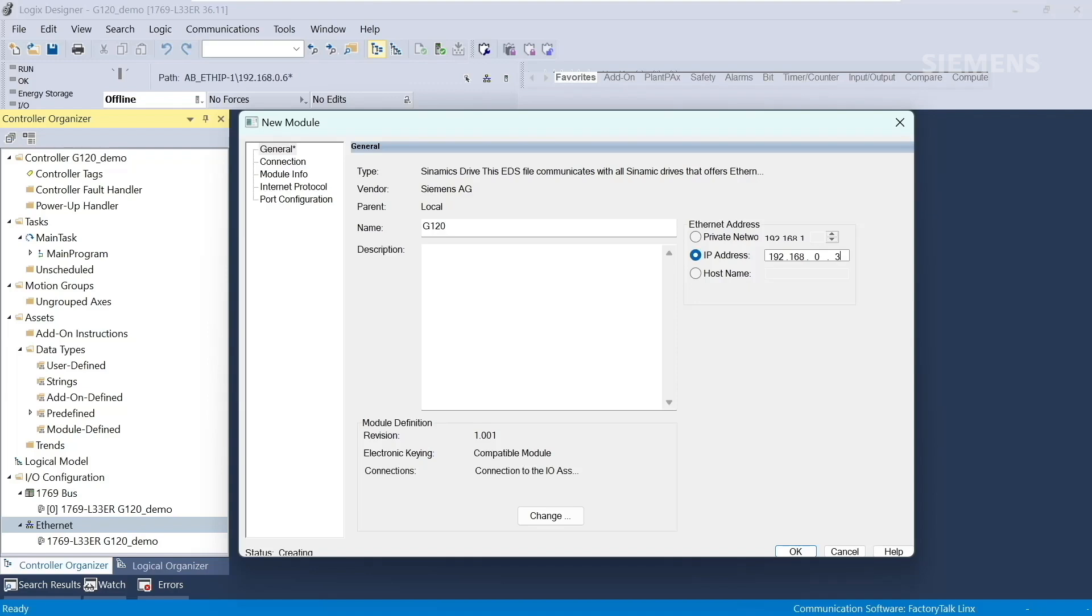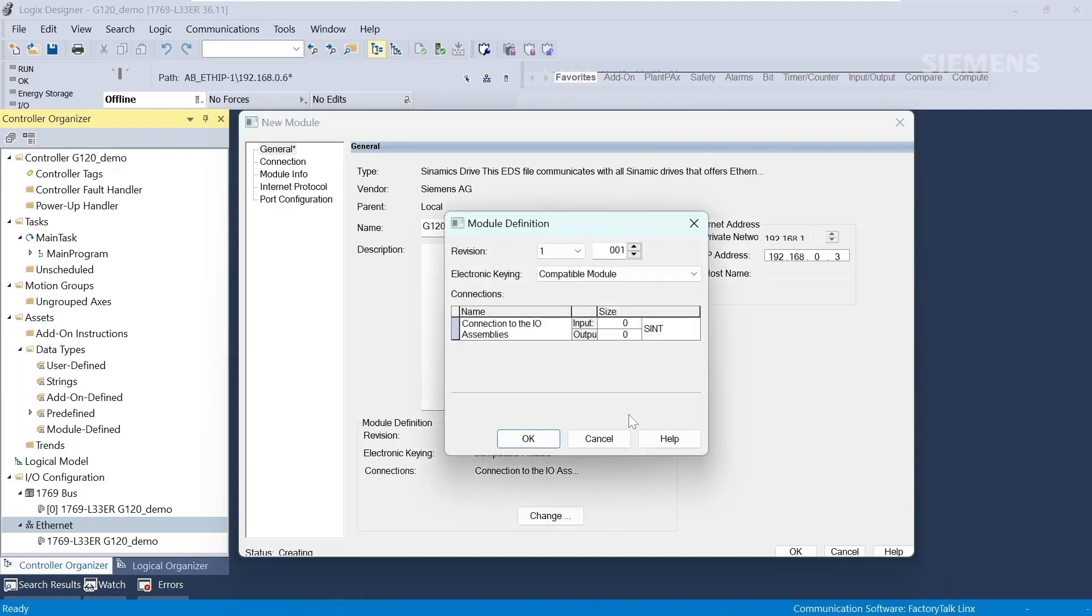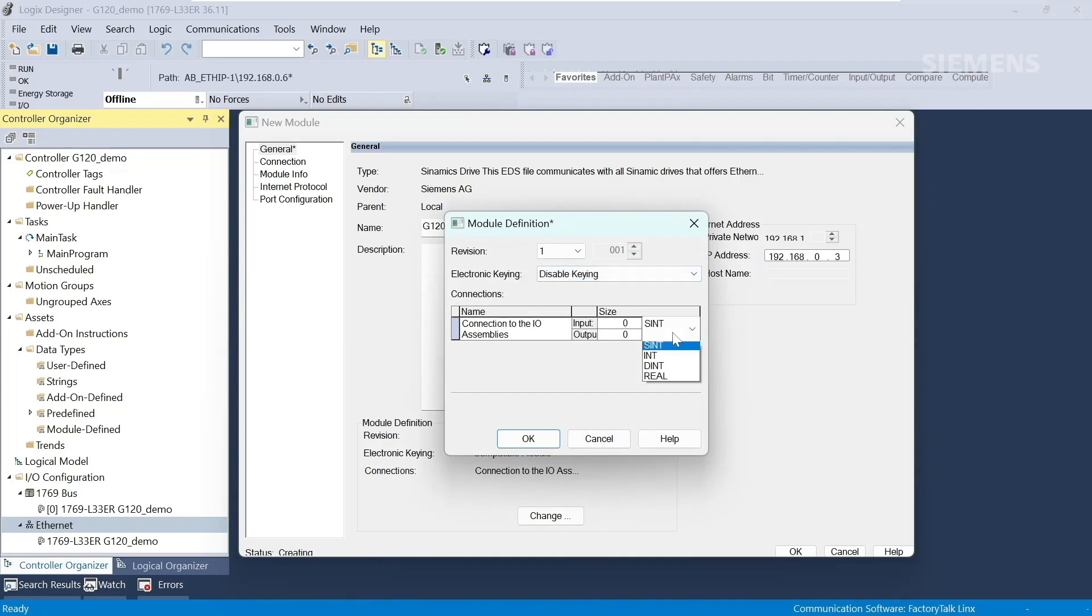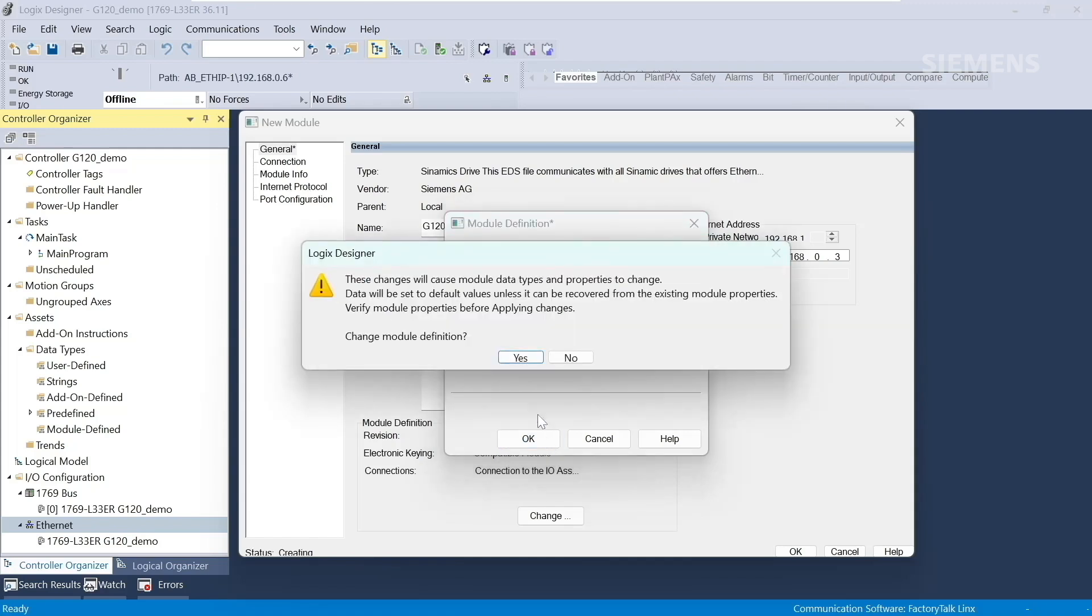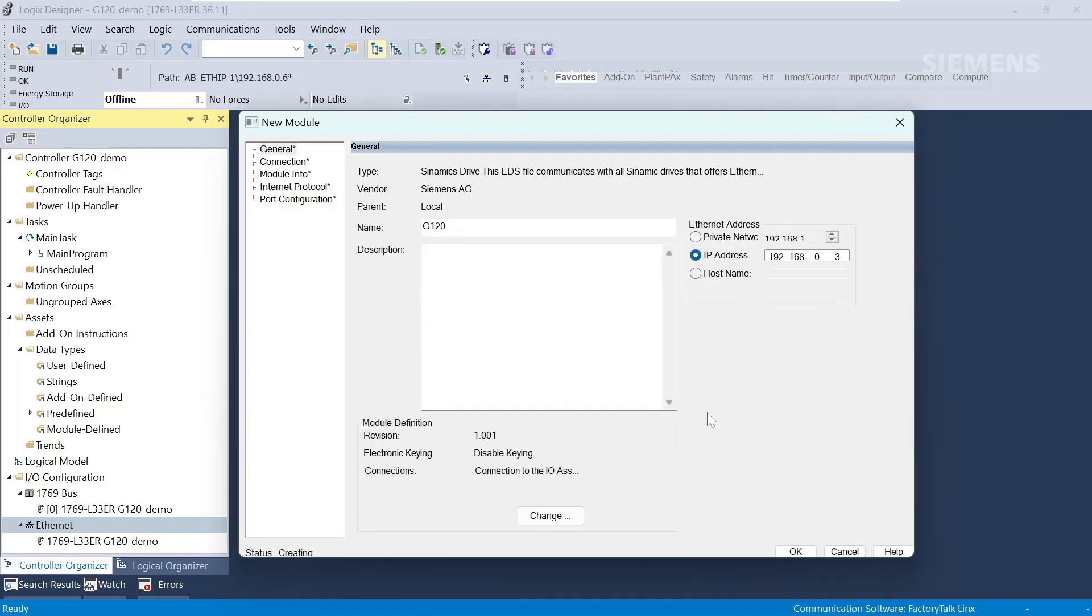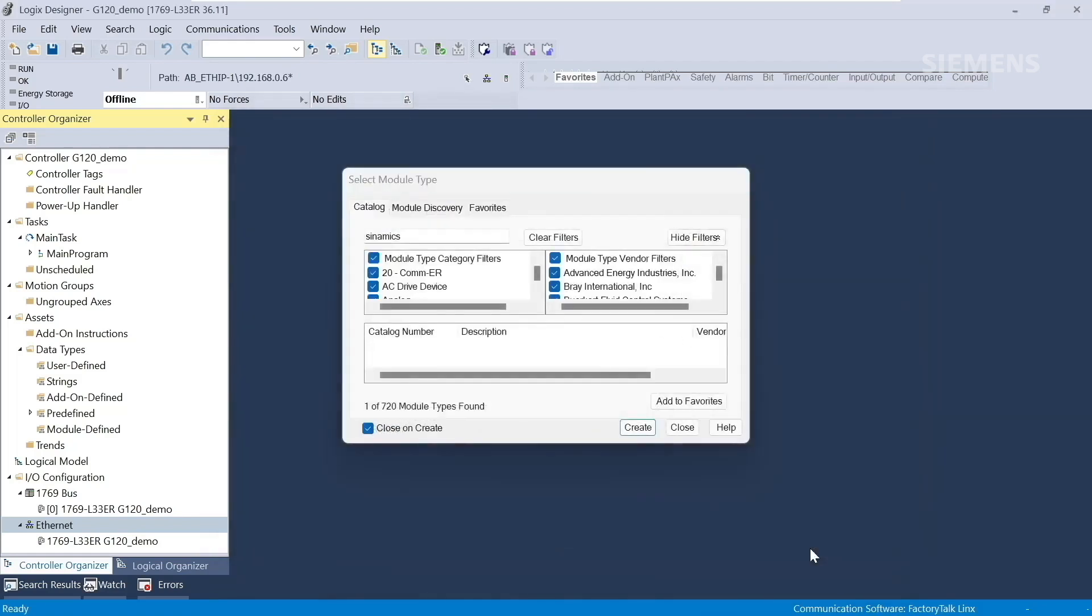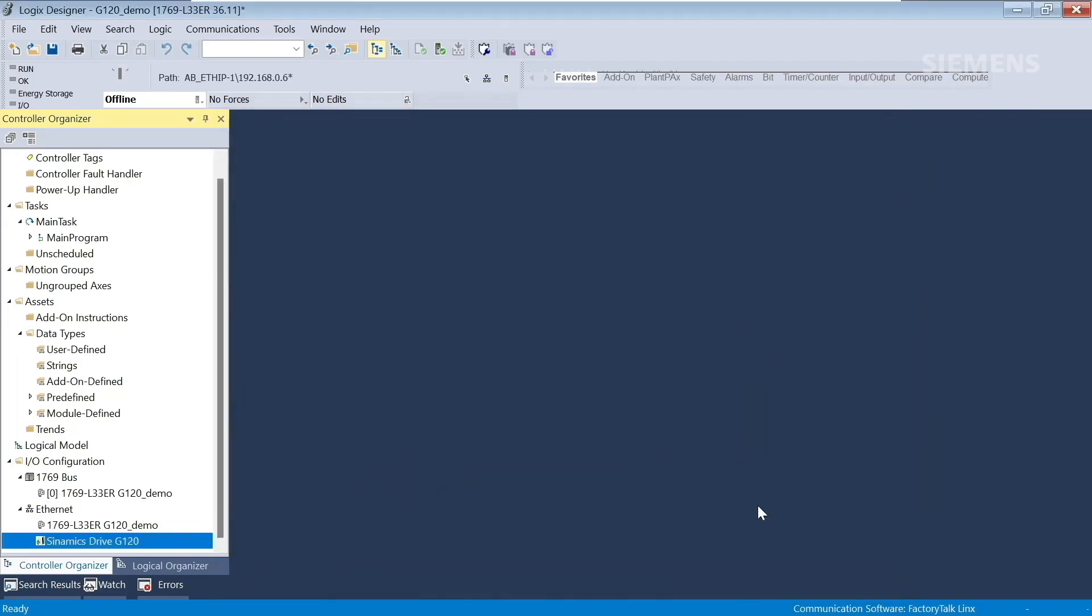Next, we'll change the module definition. We will disable keying, change the data type to int, and change the input size to 6 and the output size to 6. These selections correspond with the telegram we are using. Click OK, click Yes to change the module definition, and OK to finalize creation of the G120. The Sinamics G120 drive has now been added to the project tree.